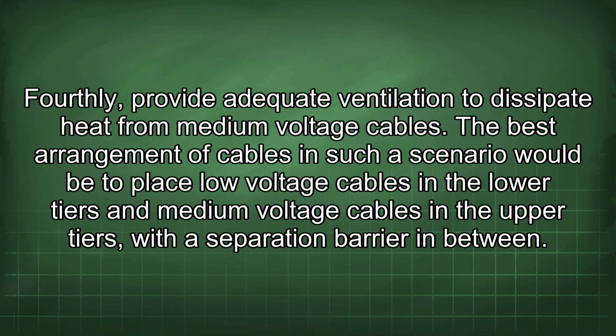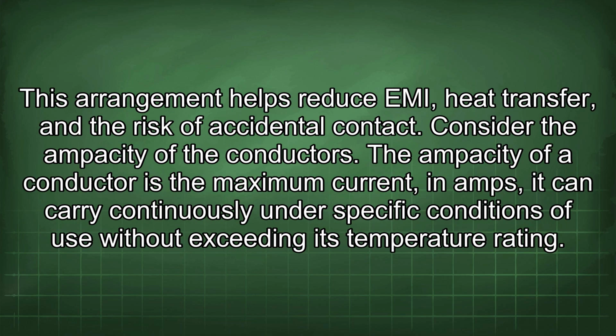The best arrangement of cables in such a scenario would be to place low voltage cables in the lower tiers and medium voltage cables in the upper tiers, with a separation barrier in between. This arrangement helps reduce EMI, heat transfer, and the risk of accidental contact.